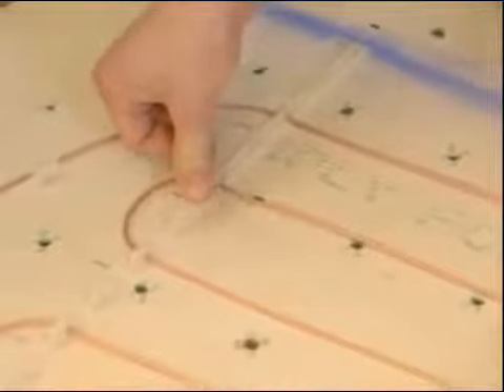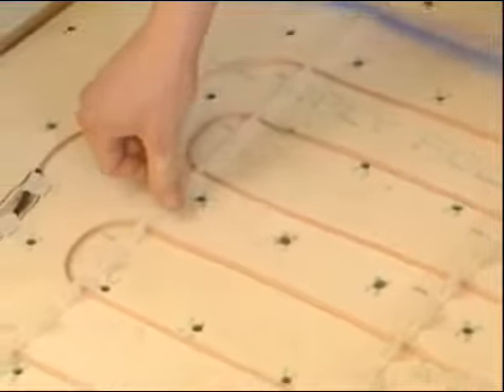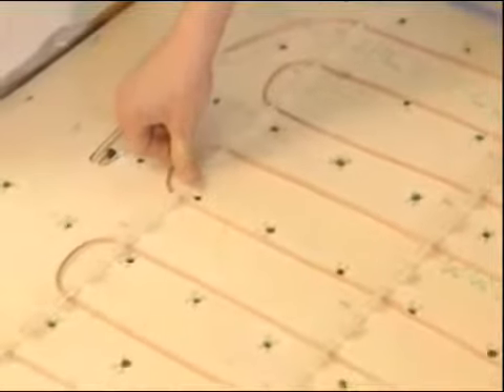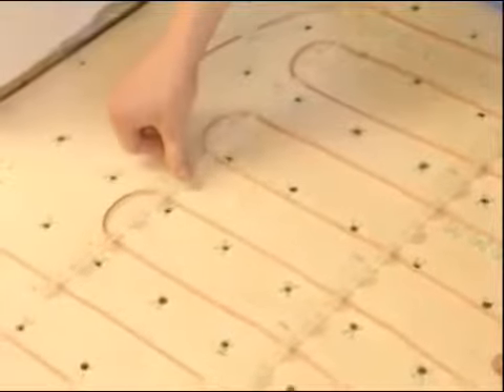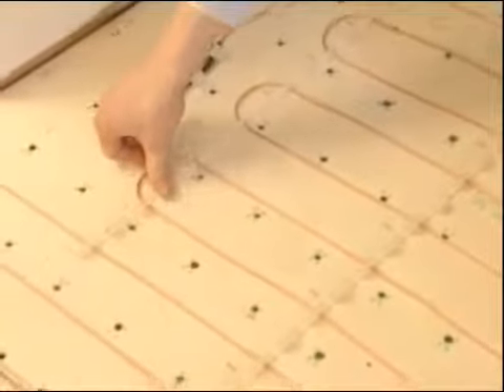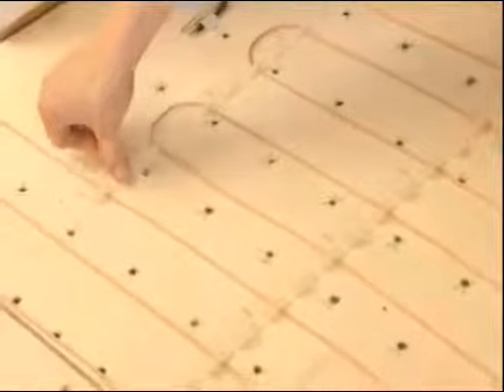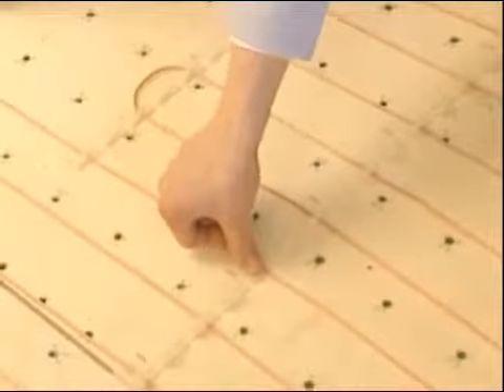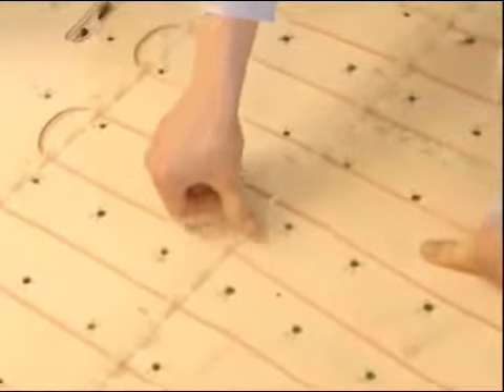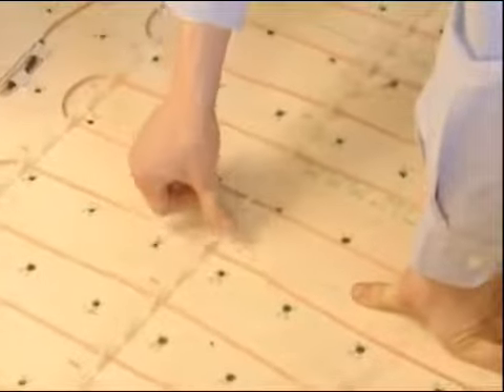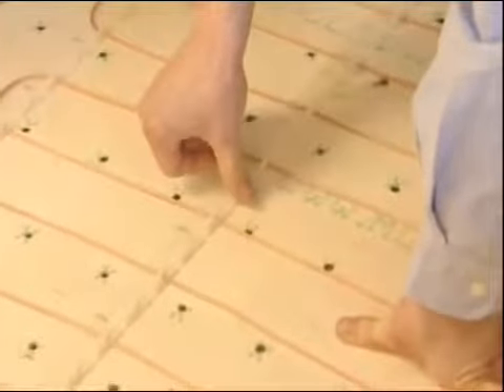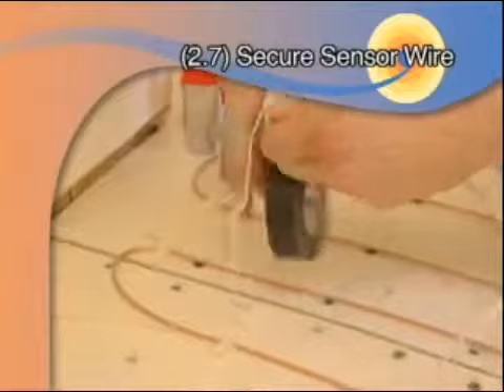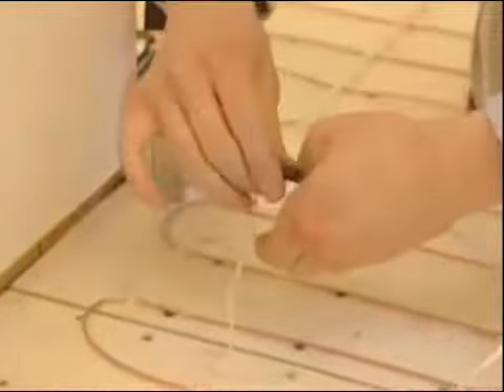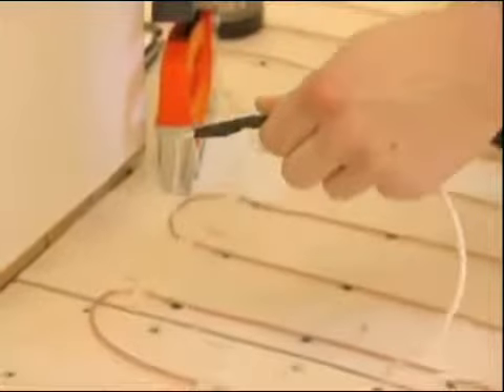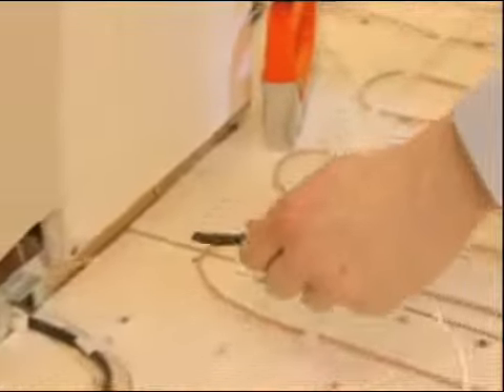Once the cable layout is completed, close all hinged clips, including the hinged clips not used, to securely fasten the cable to the floor and flatten the height of the system prior to application of the thin set. Use additional clips provided to fasten down any part of the cable that is not snug to the floor. Next, secure with electrical tape the pigtail end of the Warm Tiles thermostat sensor wire to the second pull cord and pull into the junction box.